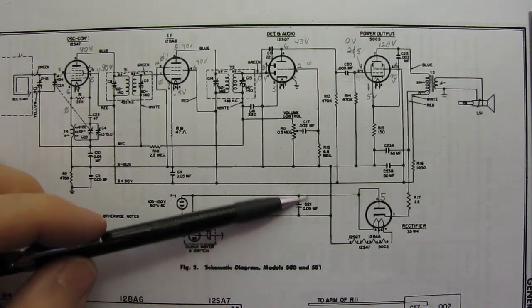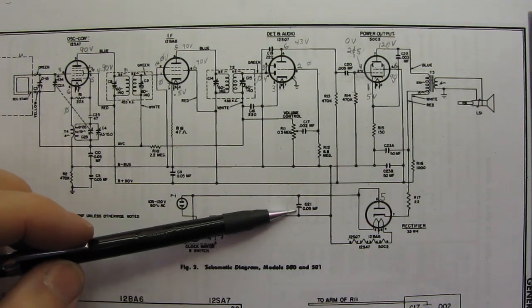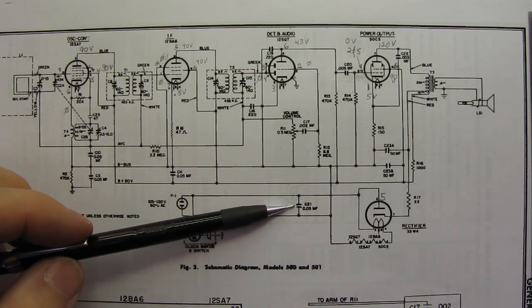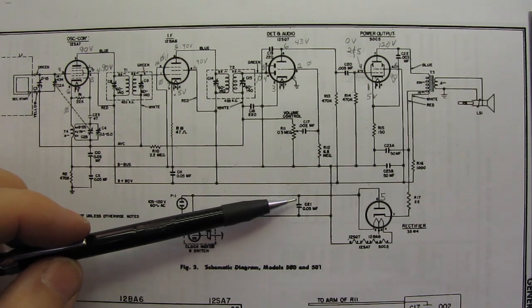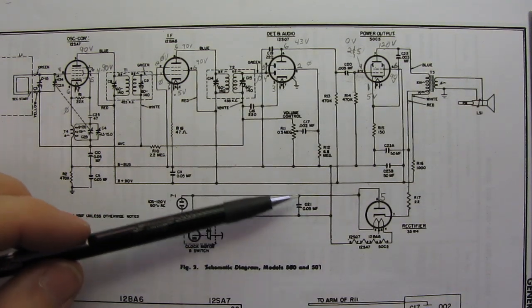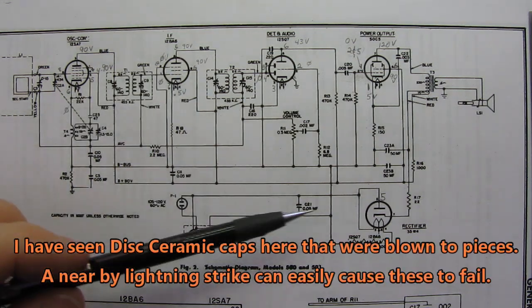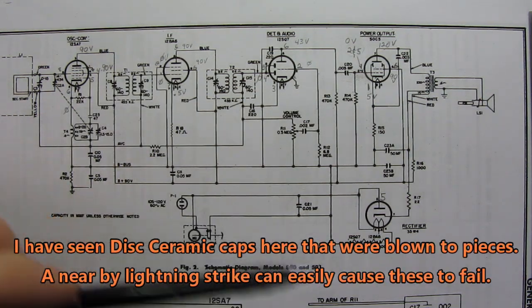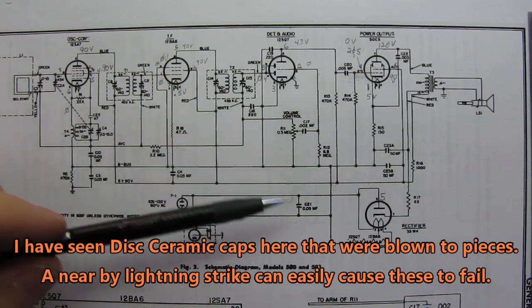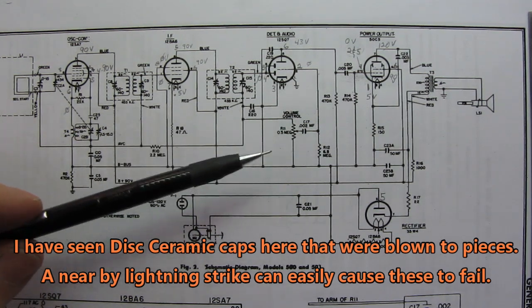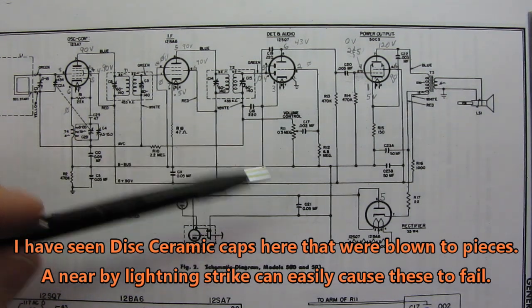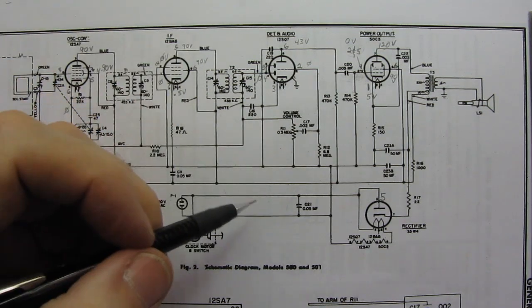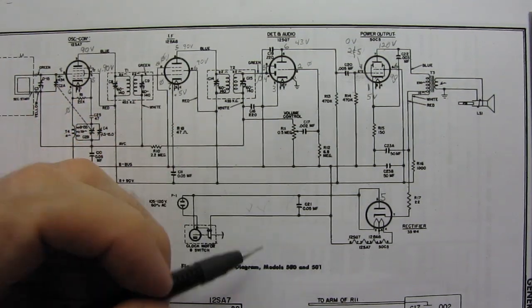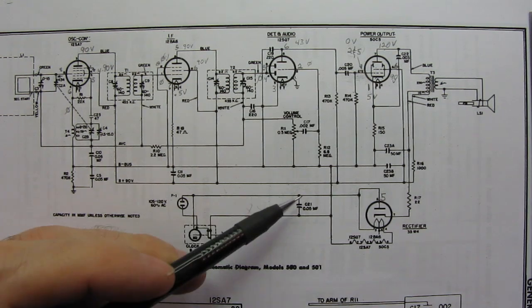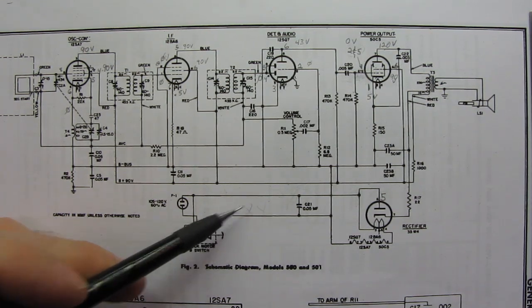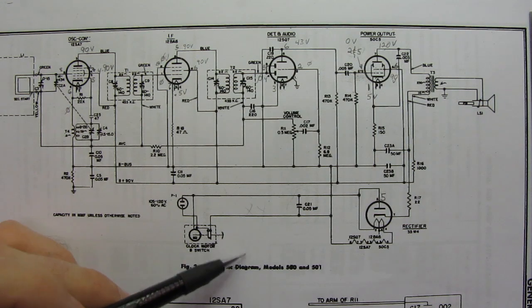This is going to be a paper cap almost every single time, and if these go, you're going to get a lot of smoke, it's going to explode basically. So just clip the lead on that. We can tolerate removing that. We'll replace it eventually with a proper X rated capacitor, across the line capacitor. You have X and Y rated capacitors. The X capacitors are for across the line, the Y capacitors are for line to ground.